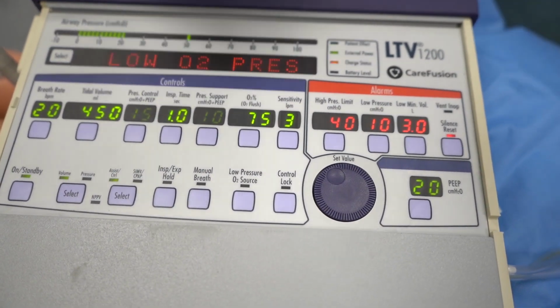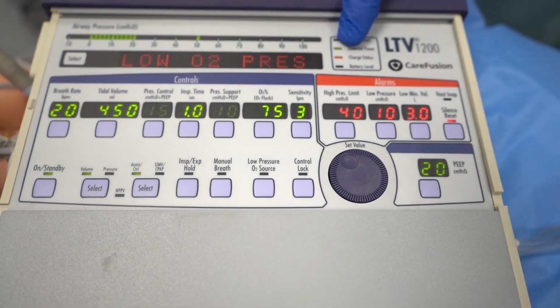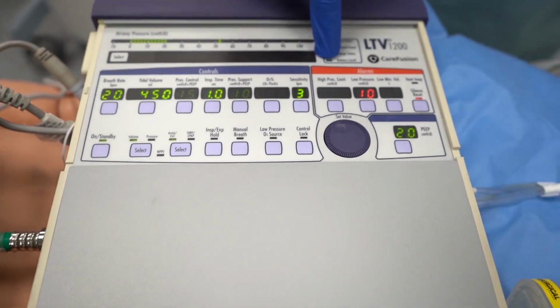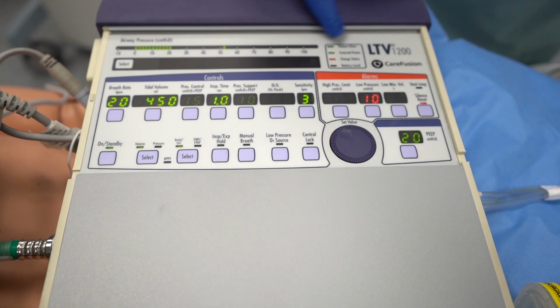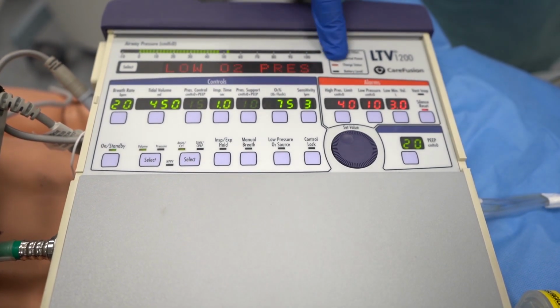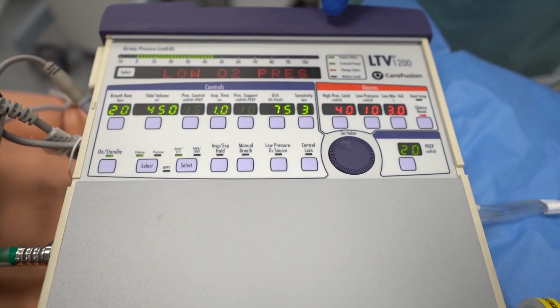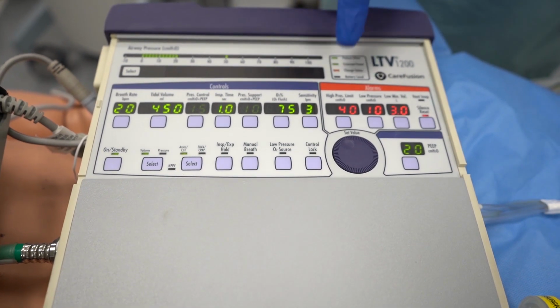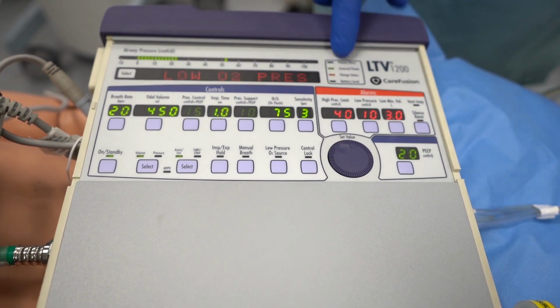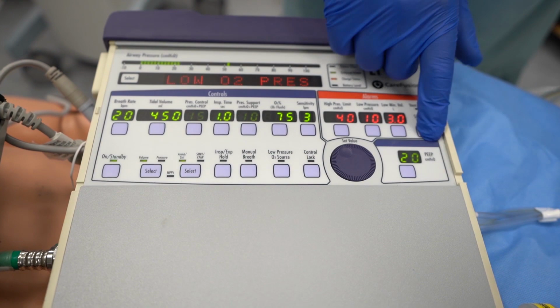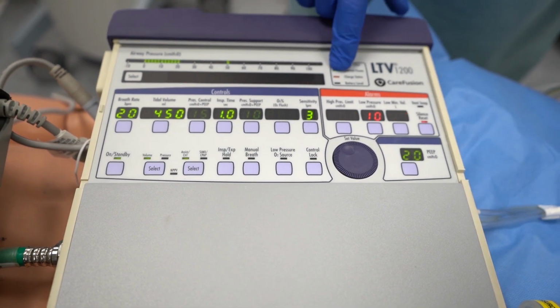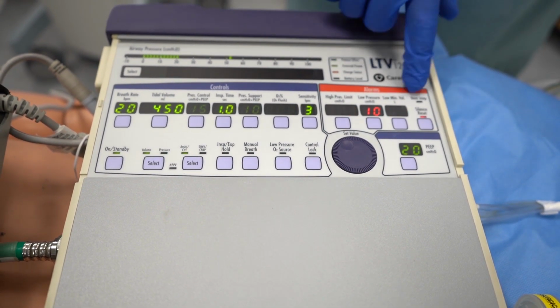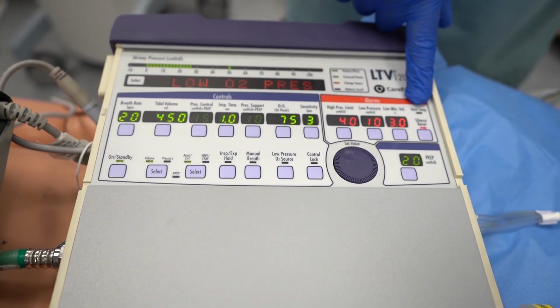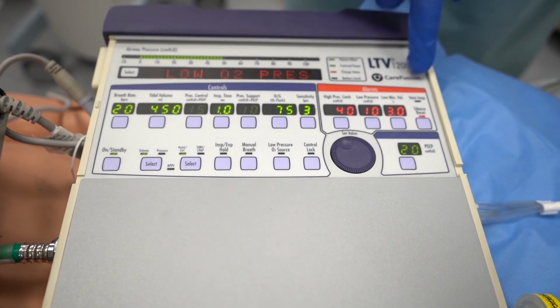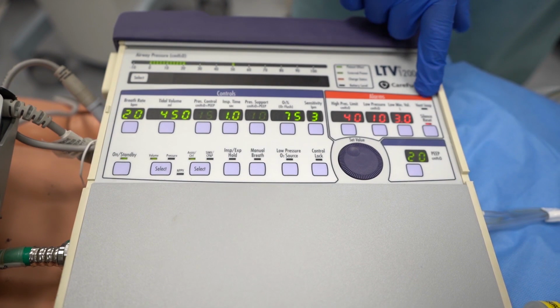As far as troubleshooting, the main thing is make sure your battery is charged. Your charge status and battery level are located in this box. Currently it's charging, so it's going to show up as orange. If your battery is low or it's about to die, so when the internal battery gets low, you actually get this vent in-op light that'll show up, and then it's telling you that you have 10 minutes until the vent actually shuts down.